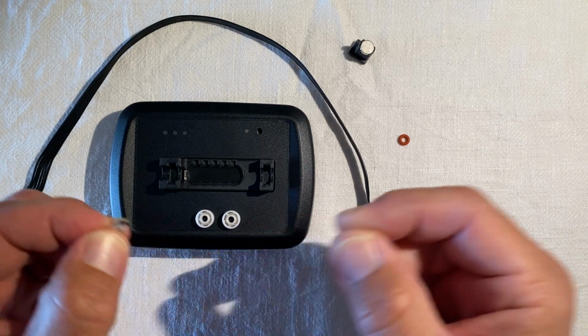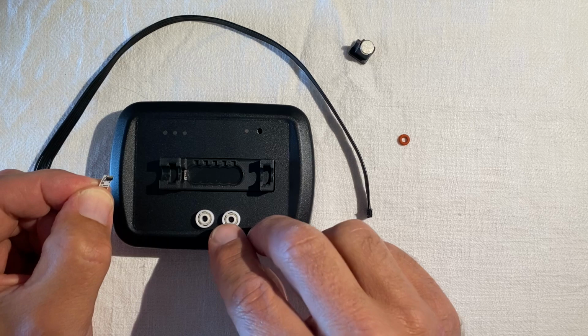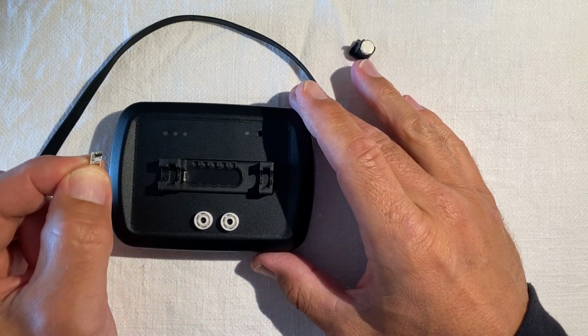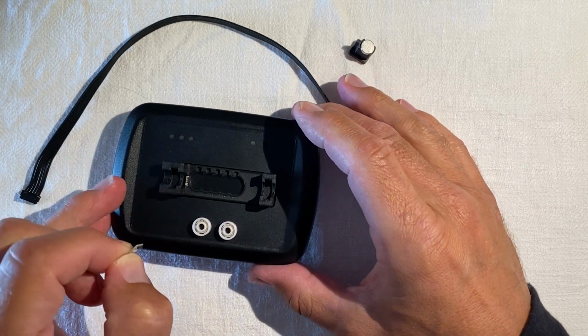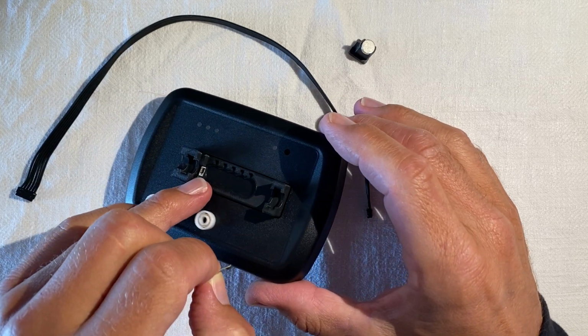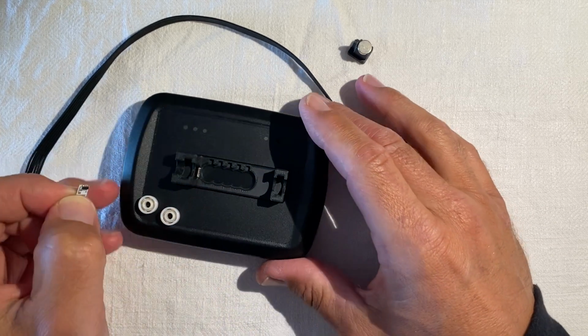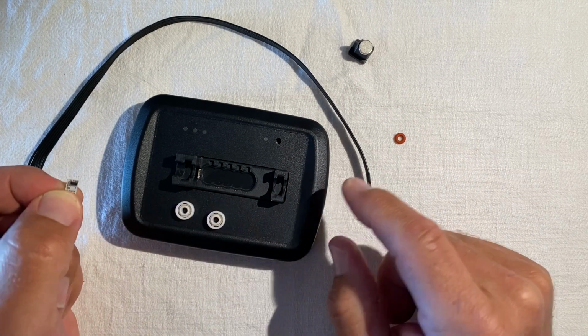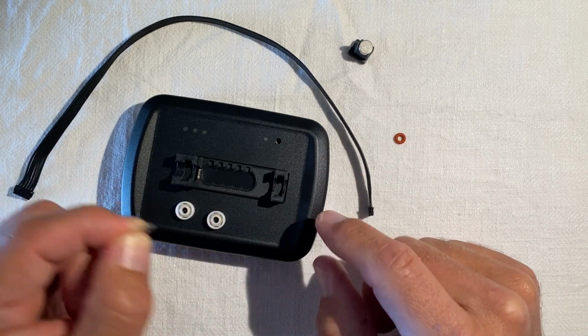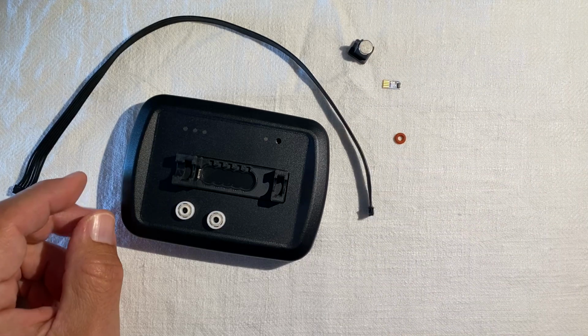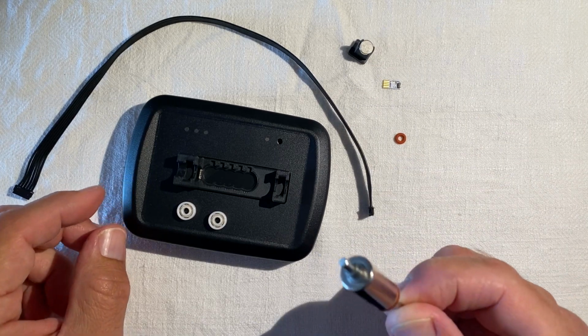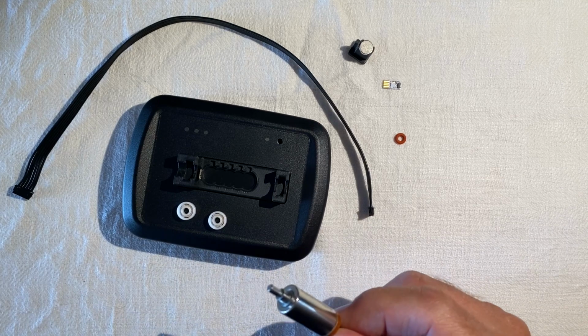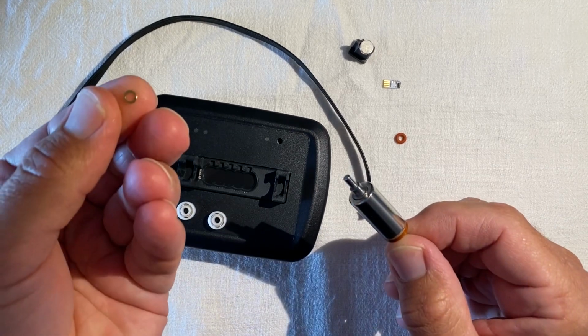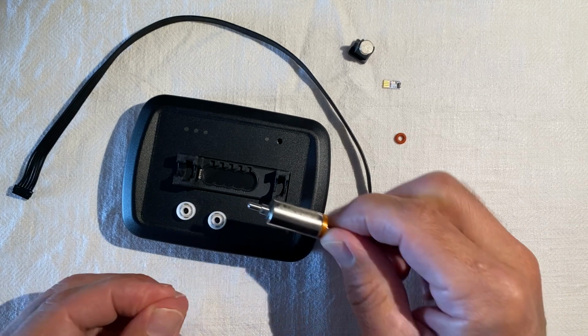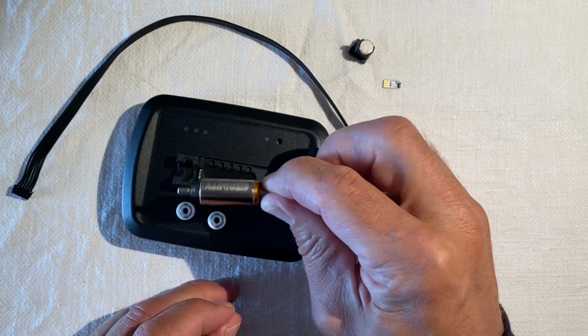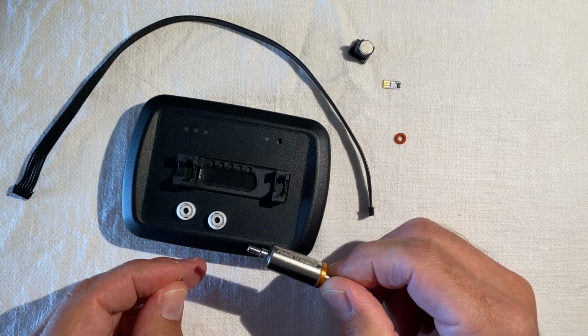And the final piece of the puzzle is the edge sensor. This sensor is mounted right on the edge. In this particular case, I already have one fitted into the box. And this makes sure that you can measure the asymmetry of the rotor. What you'll have to provide yourself is a rotor to test, and also in some cases you will need a shim to make sure that you shim the rotor properly according to the edge sensor.